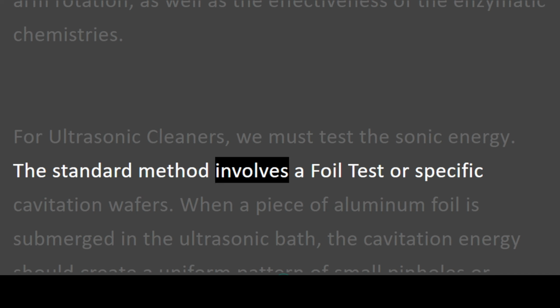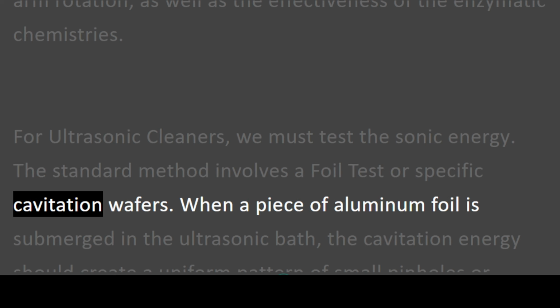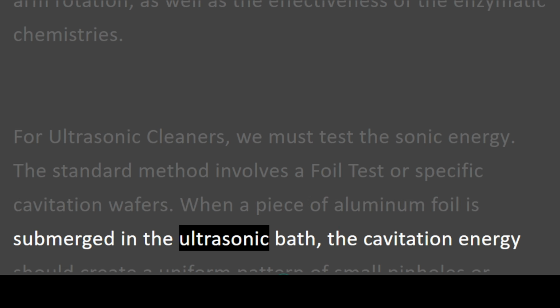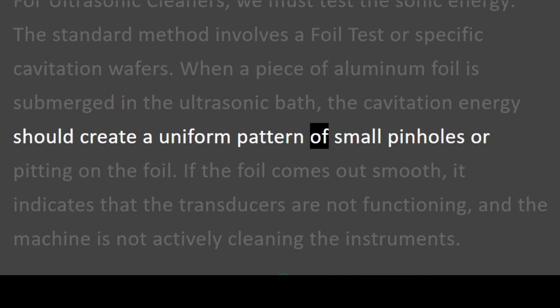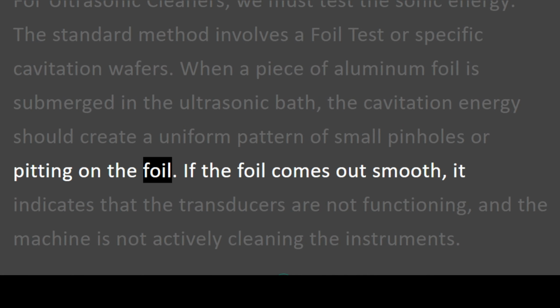The standard method involves a foil test or specific cavitation wafers. When a piece of aluminum foil is submerged in the ultrasonic bath, the cavitation energy should create a uniform pattern of small pinholes or pitting on the foil.